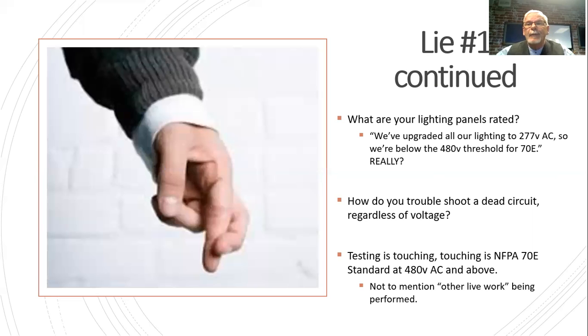Really? I'm not an electrician. I told you I'm not an electrician. Maybe you got 277 going out from the circuit breaker box, but the feed into that box is 480. The feed from the distribution panel going to the lighting panel is going to be 480. The only thing they did was drop the ground off on the individual components. That's how you get 277.